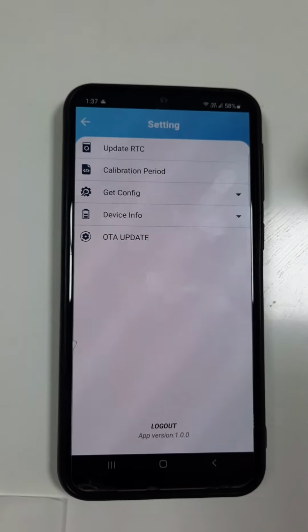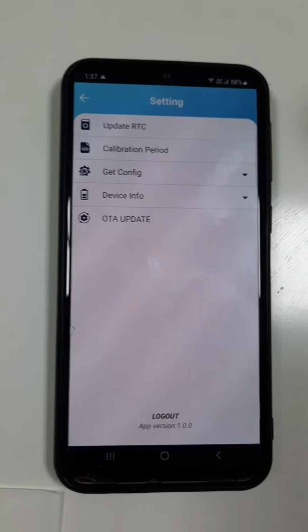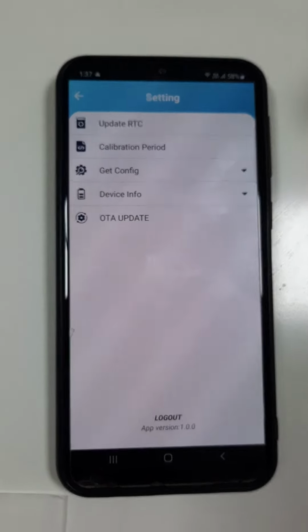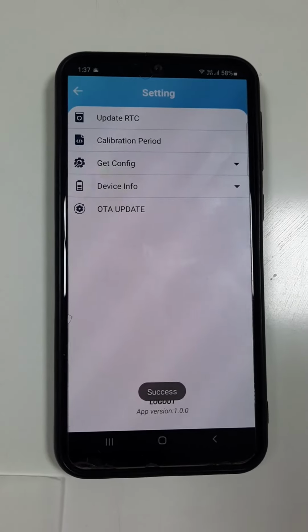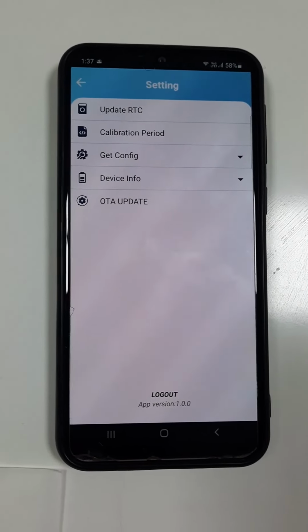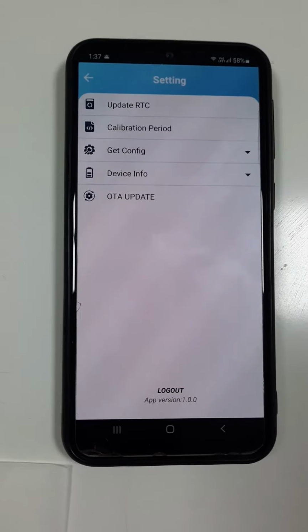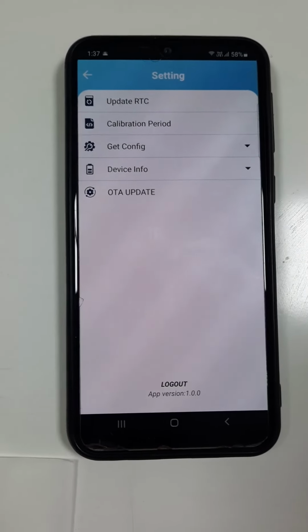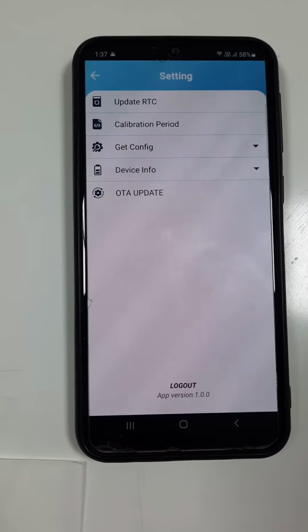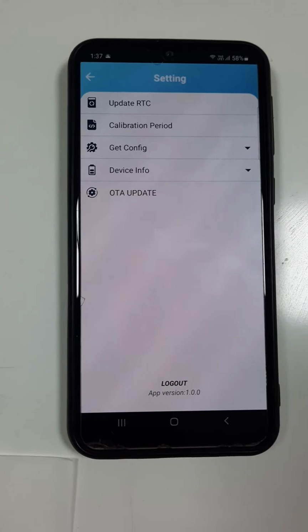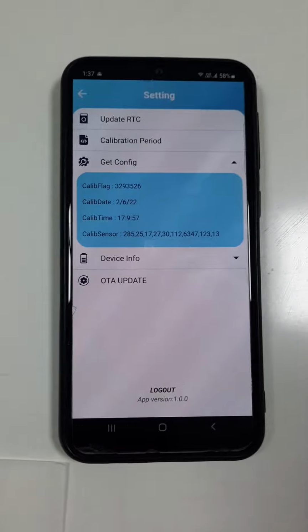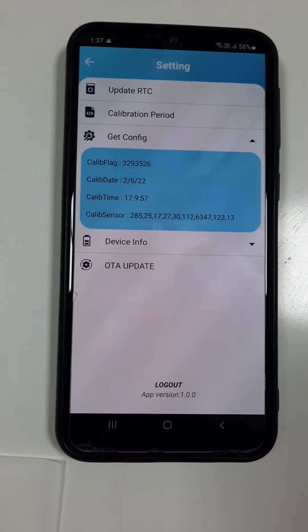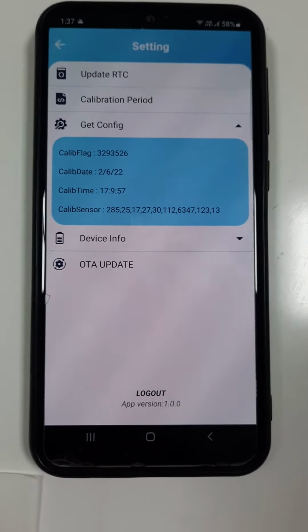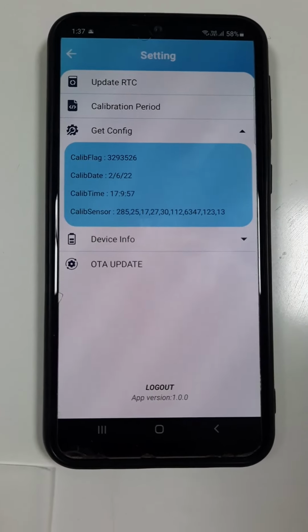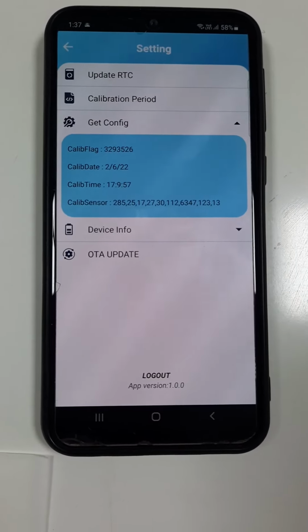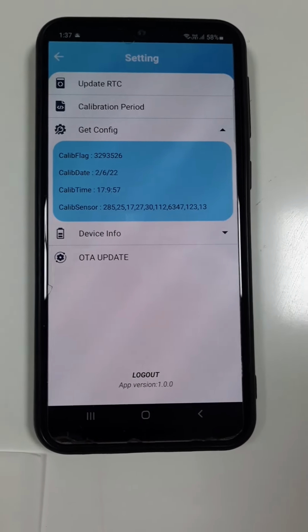As you can see, the device has an internal RTC, so with this application you can also update the RTC, the date and time of the device. When he clicks on this tab, the current date and time is sent from this Android application to the device. Now let's click on get config. This get config command is used to get the configuration of the device. You can see the various calibration parameters of the sensors and the current date and time, which is coming from the device.